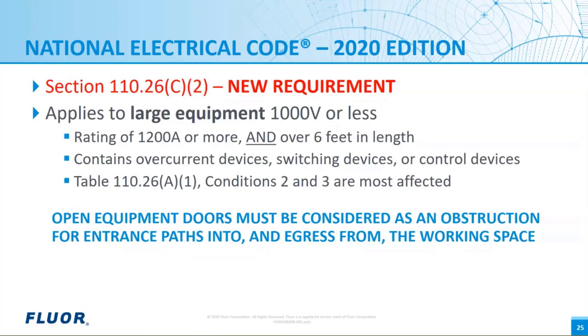This does become a major issue for existing electrical rooms and substations when the equipment is being upgraded and replaced. Now, we all know it's great to provide enough room for workers to be able to escape safely in an emergency, but there are currently no provisions for any reasonable exceptions, such as if you have the front of two pieces of equipment facing each other and one is not being worked on and the doors to it are closed. This is where a waiver or special permission from the authority having jurisdiction might be able to be used.